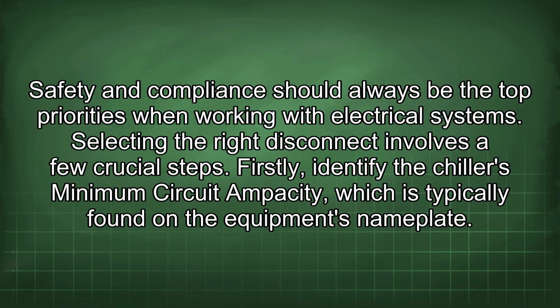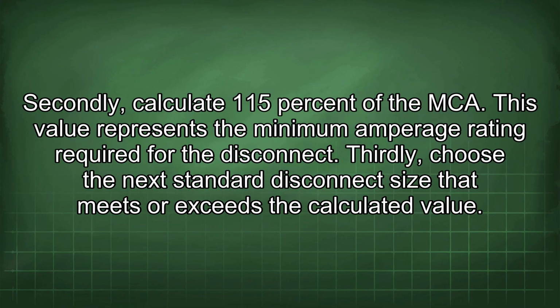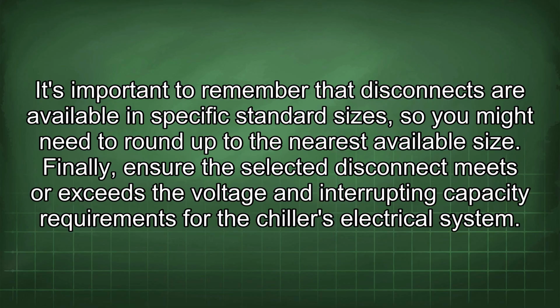Selecting the right disconnect involves a few crucial steps. Firstly, identify the chiller's minimum circuit ampacity, which is typically found on the equipment's nameplate. Secondly, calculate 115% of the MCA. This value represents the minimum amperage rating required for the disconnect. Thirdly, choose the next standard disconnect size that meets or exceeds the calculated value. It's important to remember that disconnects are available in specific standard sizes, so you might need to round up to the nearest available size.